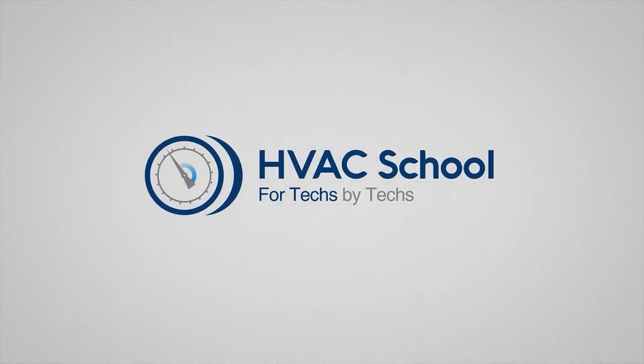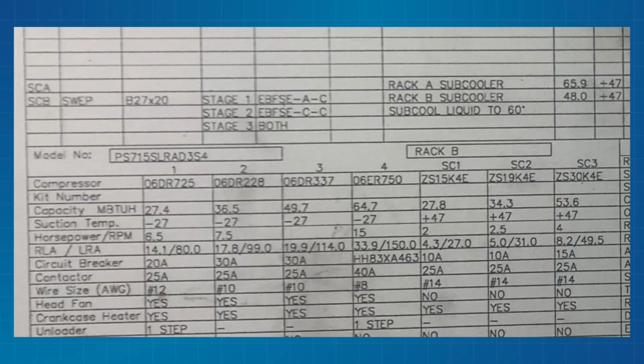That's why, right? So how much and what? I've explained this a few times in a couple different ways. Since I've got you in the classroom and we can look at some stuff, here's a legend that breaks this out and makes it really obvious. If we look at this legend, we can see I've got a Rack A and a Rack B subcooler listed on the legend. That's unusual, okay? But what this means is I've got a satellite subcooler on this rack, and it's subcooling A and B rack. That's what it's doing. Since we're doing that on this store, they all work this way, and it's going to put it all in the same legend, which makes it really easy to see. Found this the other day by accident. I was looking for something else, so I was like, perfect for class. Very happy that I stumbled on that.